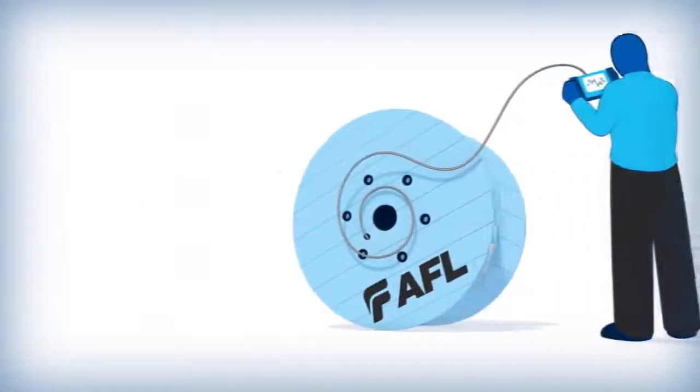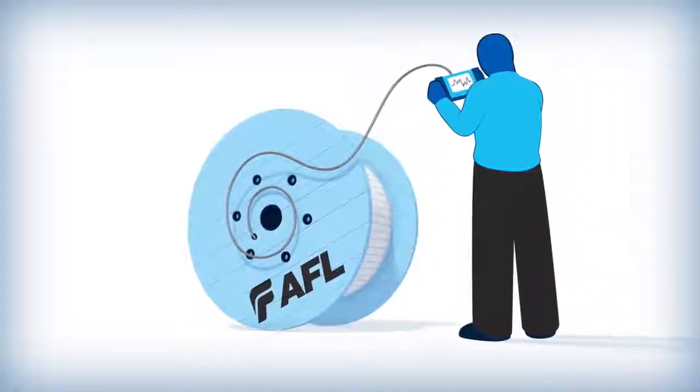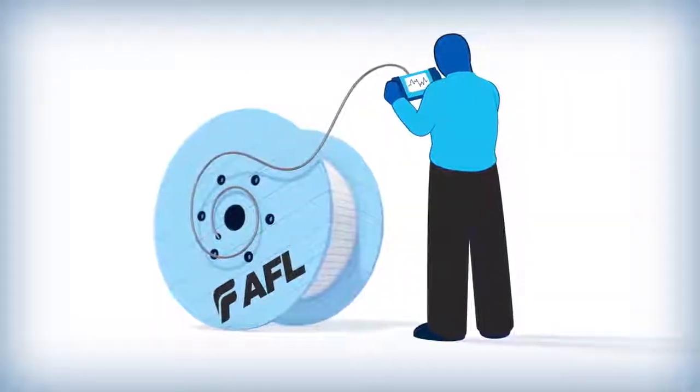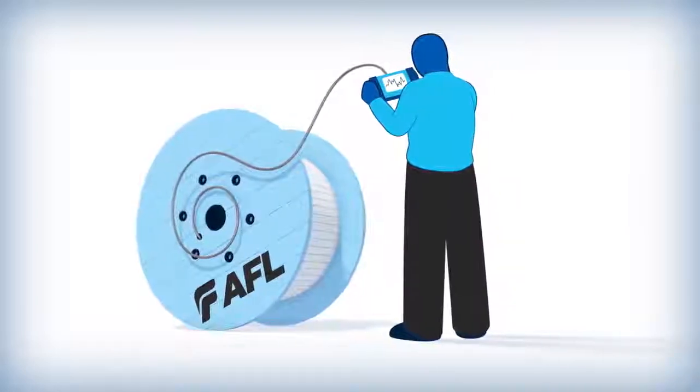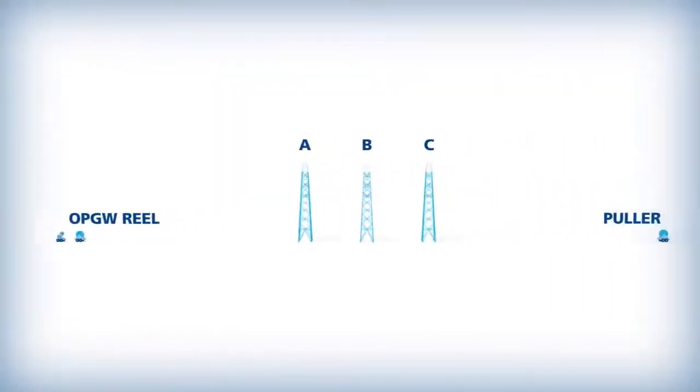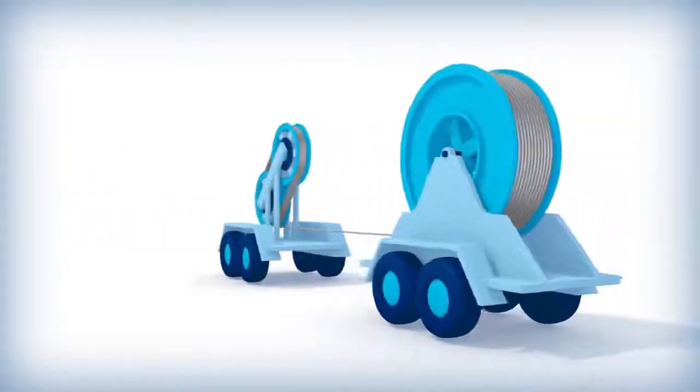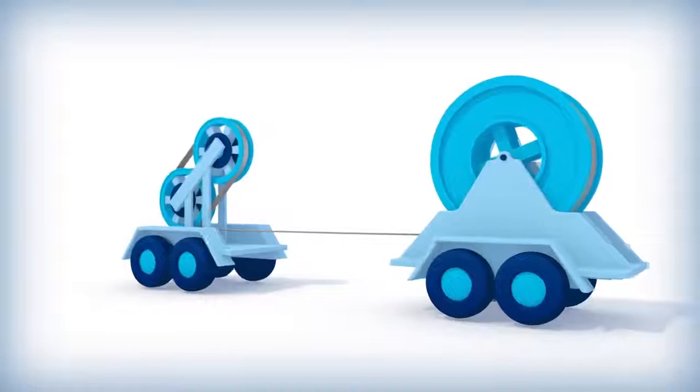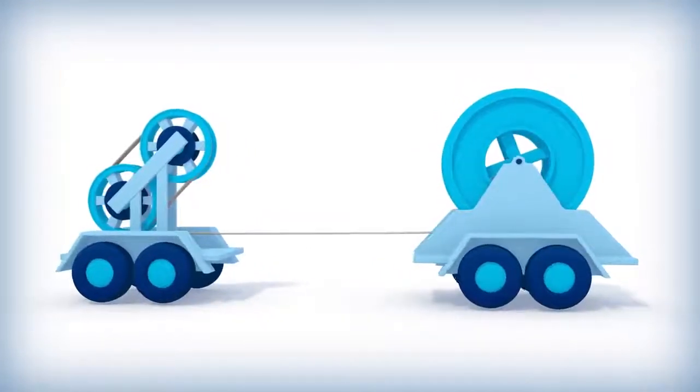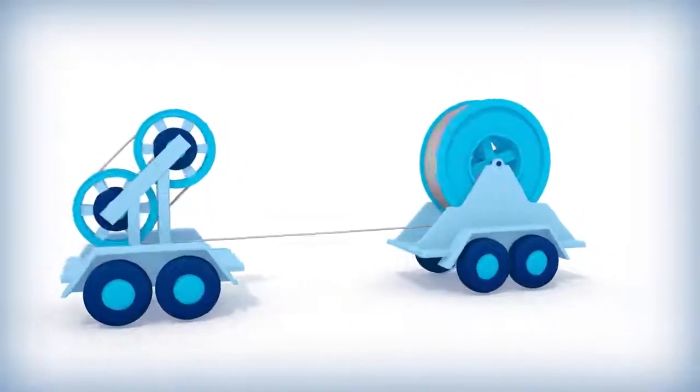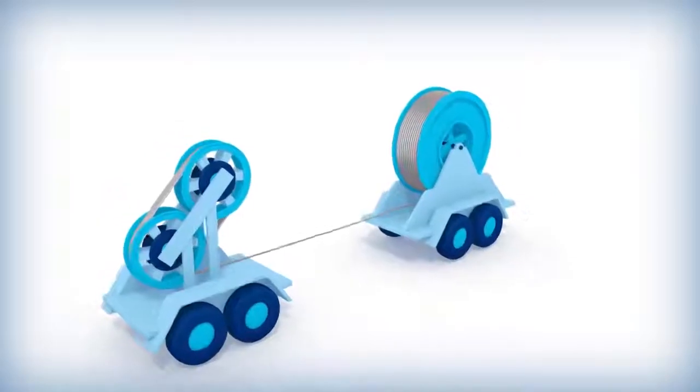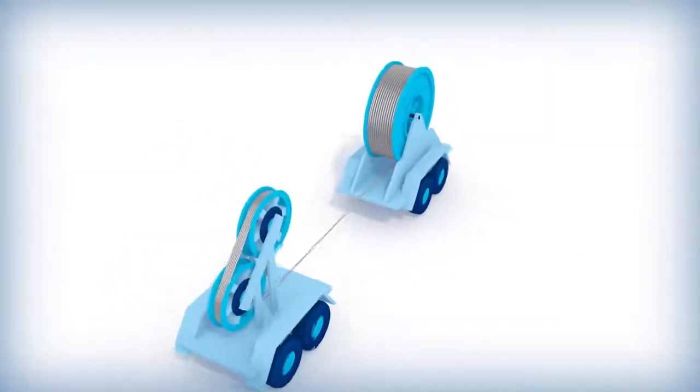To ensure the OPGW has not been damaged, it should be tested prior to and after installations. AFL recommends using the controlled tension stringing method. Because the OPGW reel is not designed to withstand the braking forces that arise during stringing, AFL recommends using a multiple groove bullwheel tensioner.